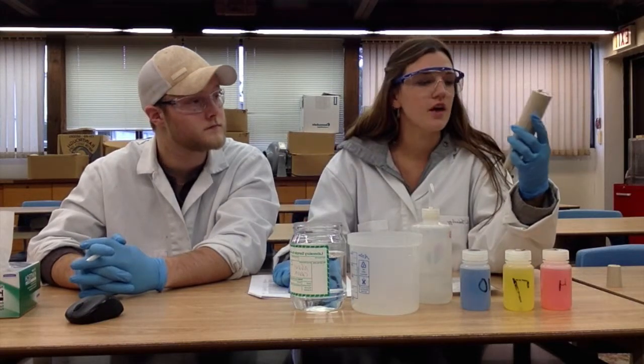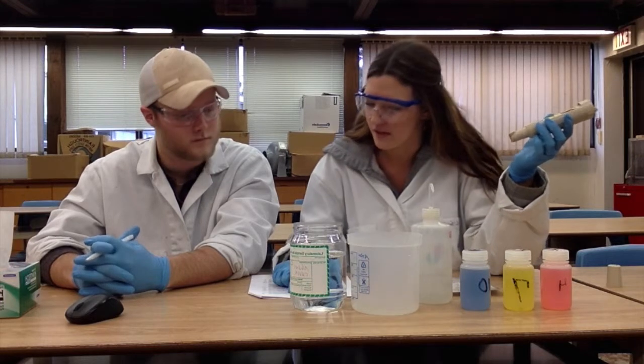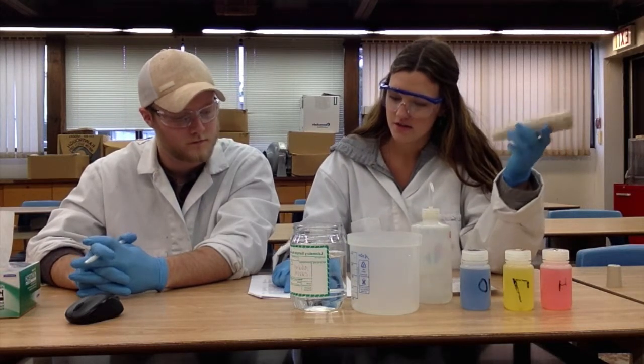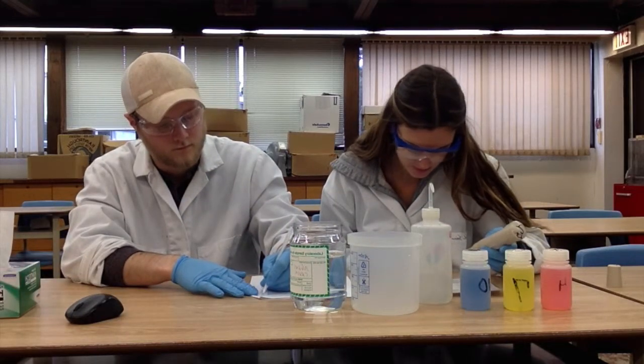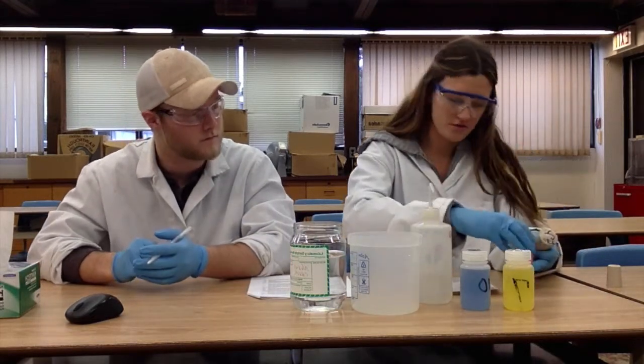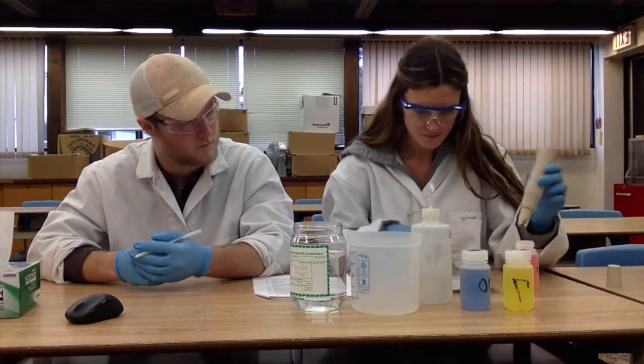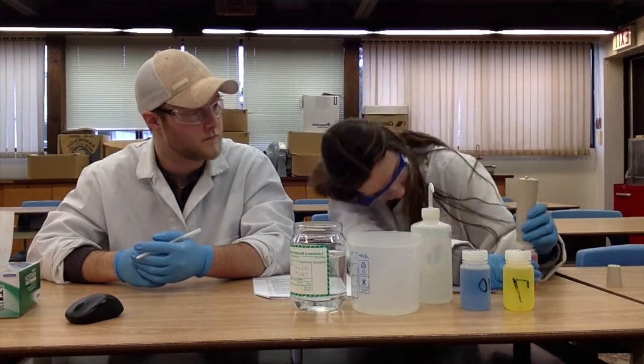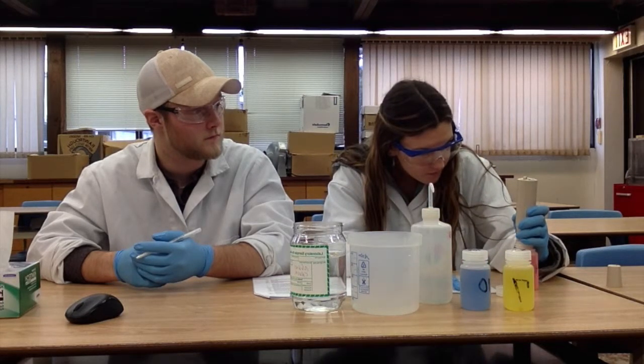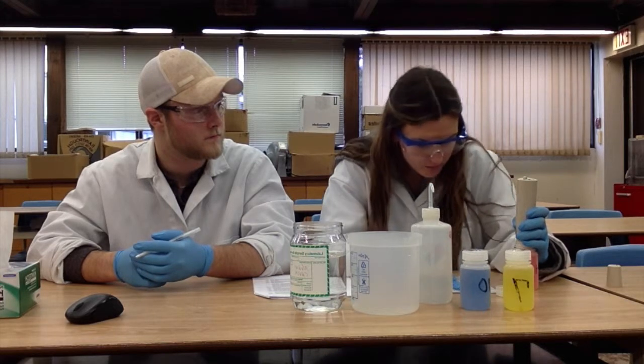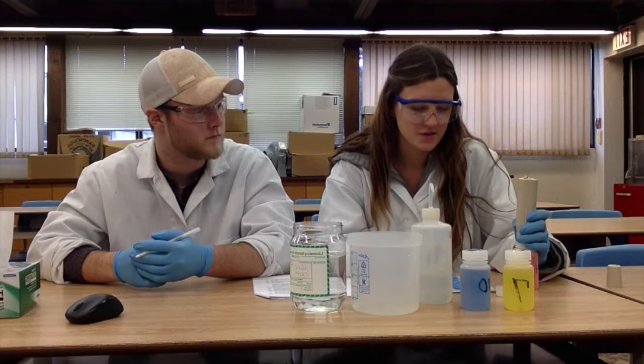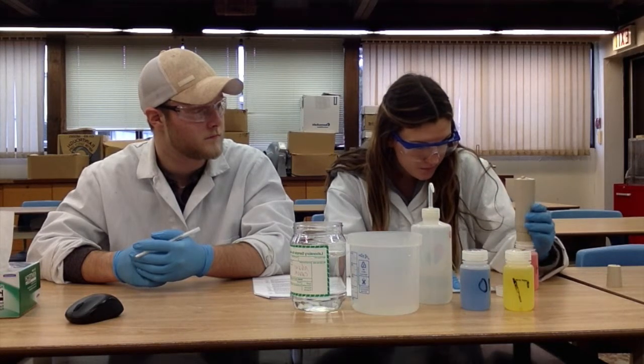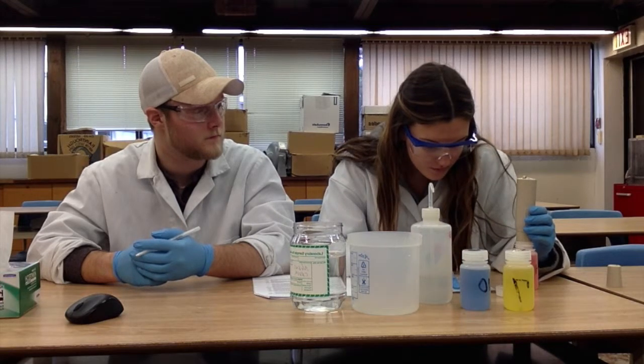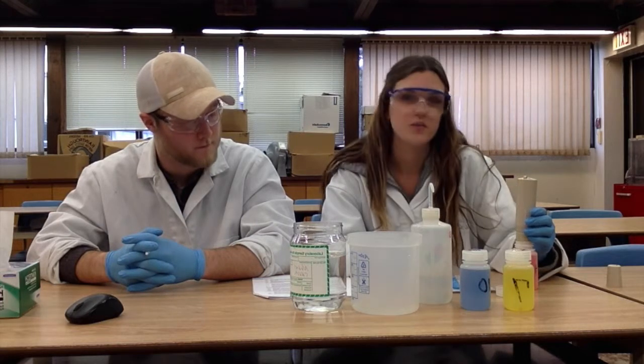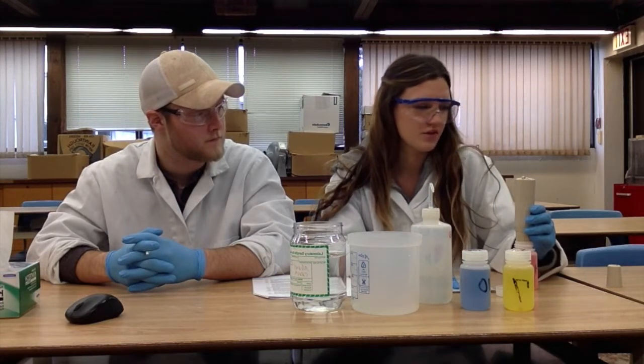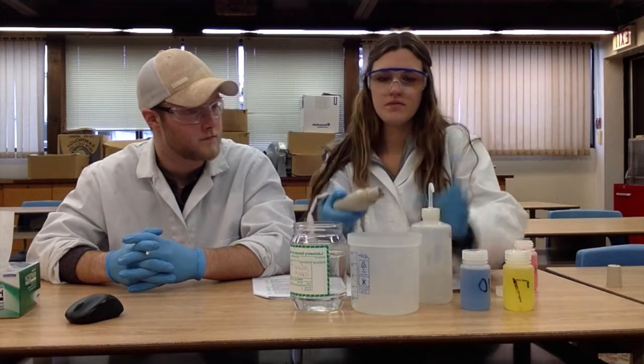Okay, so now I'm doing pH. And the battery power is okay. And we don't have to put in the probe, it's already in there. And then I cleared the previous standards. Now I'm going to calibrate it. Okay, so first I'm using a 4. Okay, and allow 2 minutes for the test to stabilize. And then I'm going to push hold to confirm the calibration. And then rinse off.